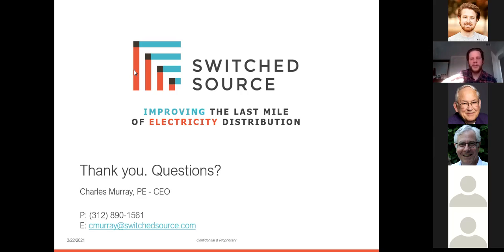The last piece is backfeeding the substation, which most utilities see as a tremendous cost—it can be one or two million dollars to upgrade protection schemes to handle backfeed. In those cases, we do some balancing of real power flow from distribution circuit to distribution circuit, and put an automatic voltage regulator on the side of the device closest to the solar facility to help regulate voltage. Solar facilities these days may have requirements to maintain current carrying capacity so they can regulate their own voltage using reactive power output. That's the use case we focus on with solar.